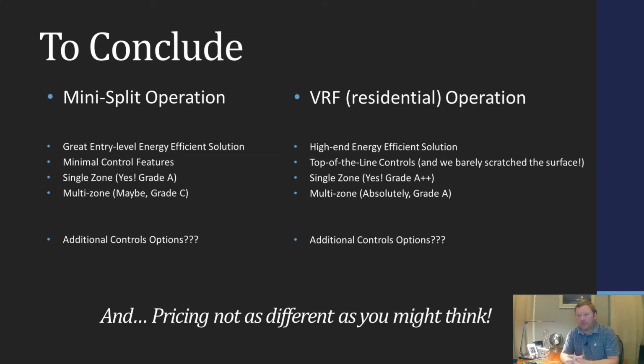So to conclude, mini split systems, great entry level product. Super efficient because they use the inverter technology. And when you look at a mini split system, if you have it in 1 zone because you just want to provide supplemental heating or supplemental cooling, maybe to the master bedroom, because the house has a ducted system but it doesn't quite reach the master very well, that's a great option. When you start looking at 2 zones or 3 zones or 4 zones on a mini split, you just need to know up front that you better set all of your set points and then leave them there and don't ever change them, because you have to maintain, otherwise you could very easily have overshooting occur because of the lack of controls the mini split has.